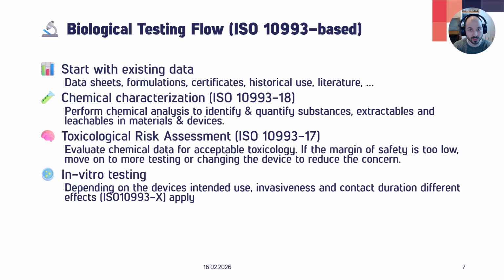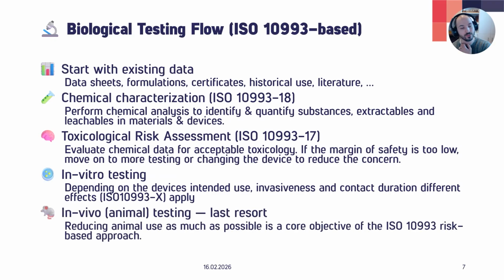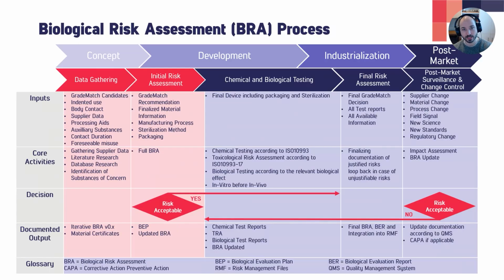And if the device's use justifies or necessitates further testing, such as chronic toxicity or whatever, we can also go and do that. And then in the end, we will do in vivo animal testing. And the ISO 10993 also makes sure that we do the minimum animal testing possible. The ISO 10993-2 is about animal safety, and that you need to go through an ethics committee to get to animal testing. Good. So this is basically the core slide, which summarizes the biocompatibility process in general.